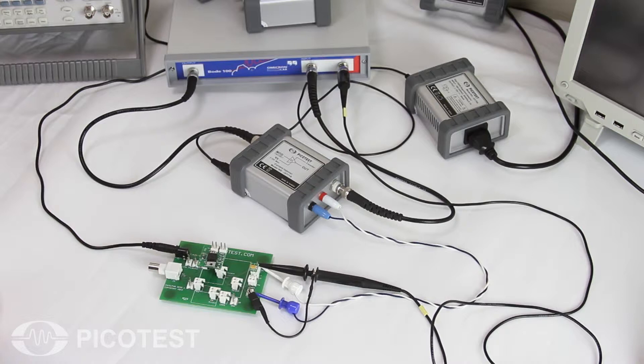The 50 ohm current monitor port on the current injector allows us to easily monitor the load current with an output voltage representing 1 amp per volt.